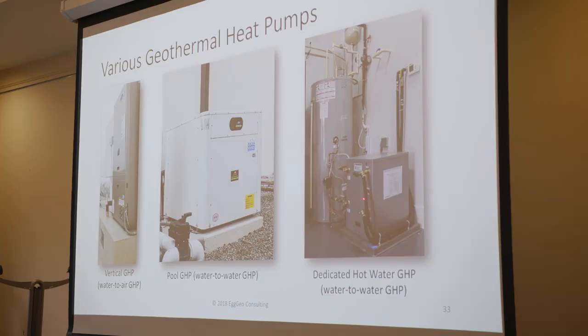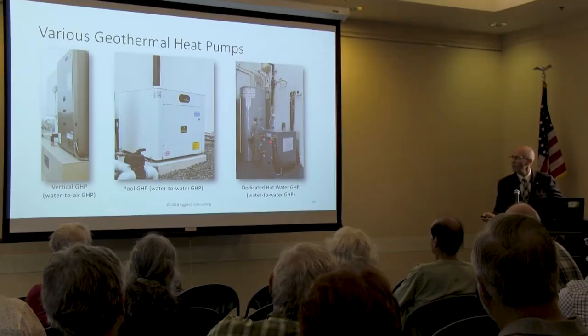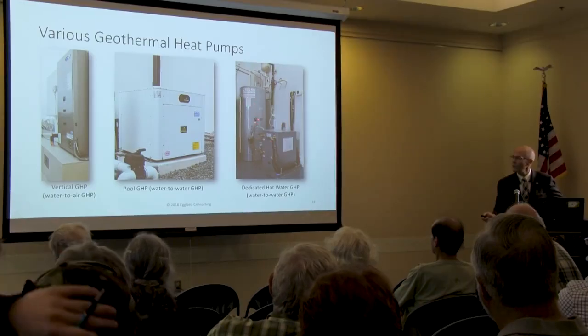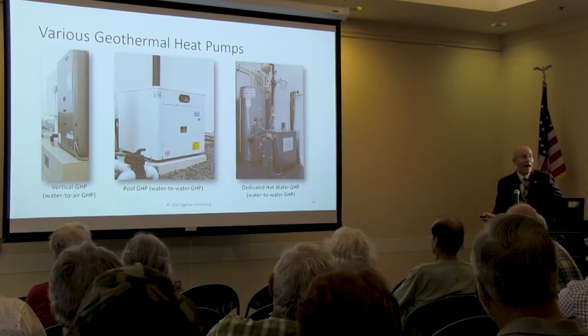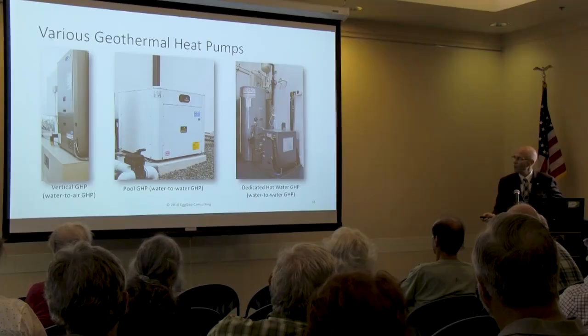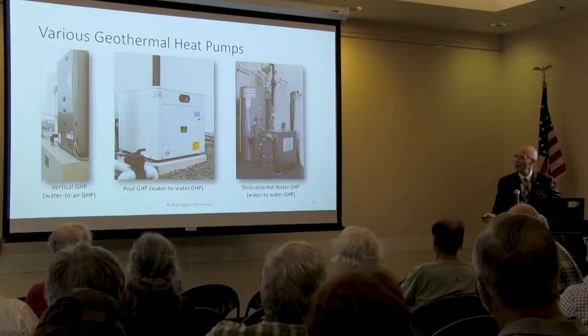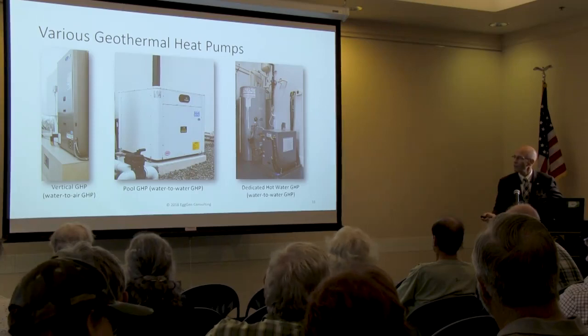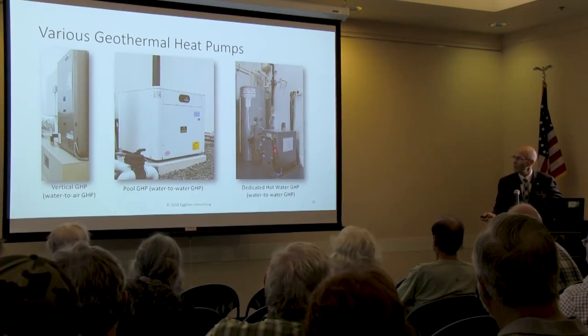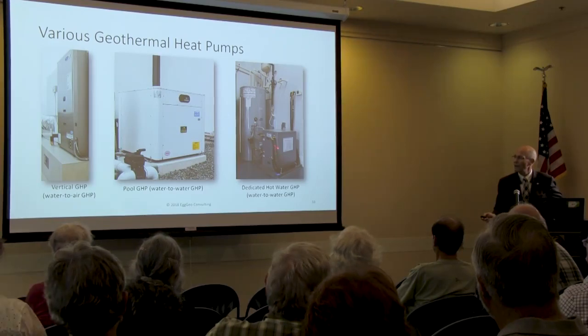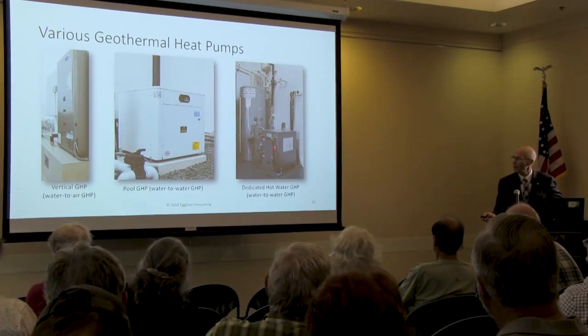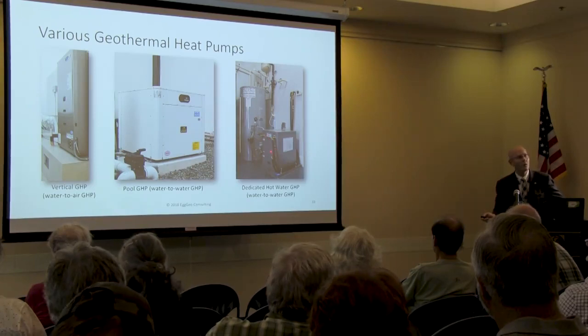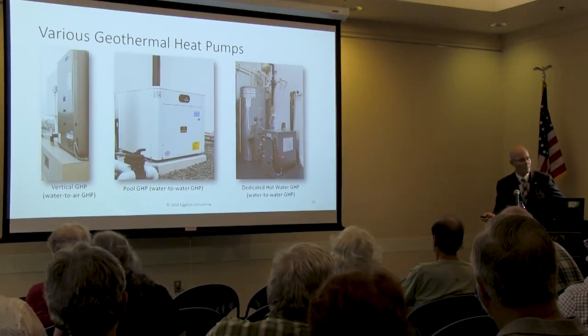This is a 90,000 BTU heat pump that can make 5 gallons per minute of hot water at 140 degrees continually. It's got a tank here just to regulate the temperature, but this is in a house. This is a larger house, granted. Most people don't have to have a dedicated domestic hot water heat pump. Most of them can get their hot water just from the waste heat, but this gentleman decided to do it. Many restaurants and commercial buildings have dedicated domestic hot water heat pumps, but this could also be used to do radiant cooling or radiant heating in a building.